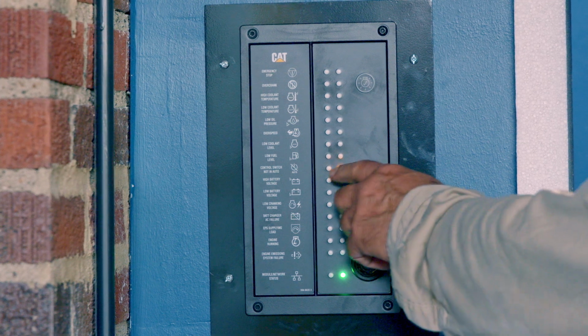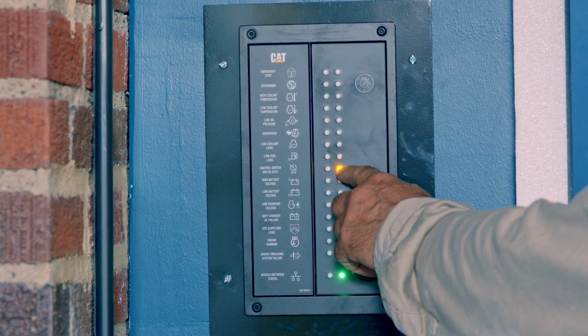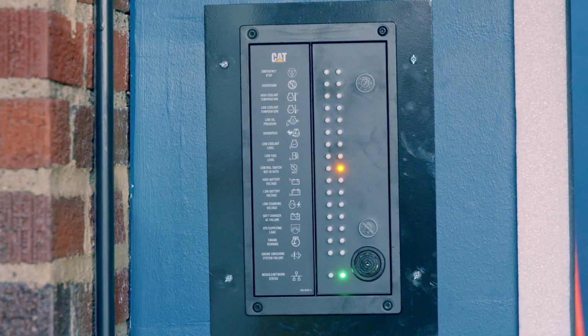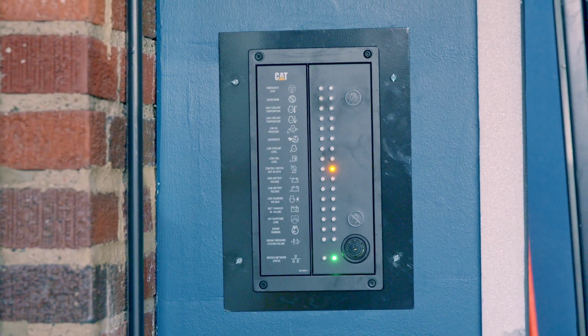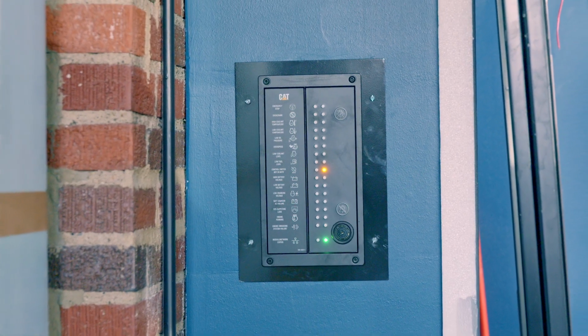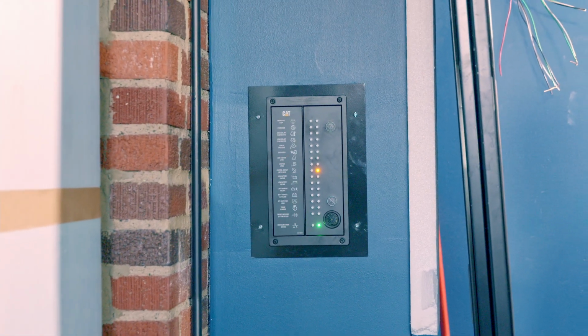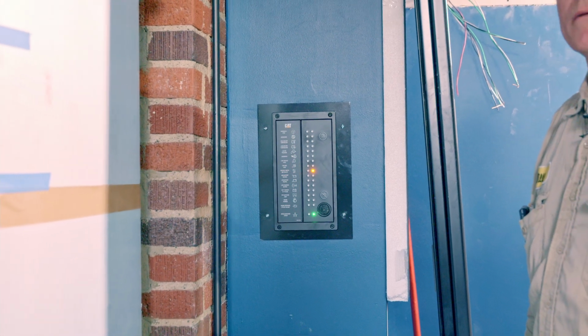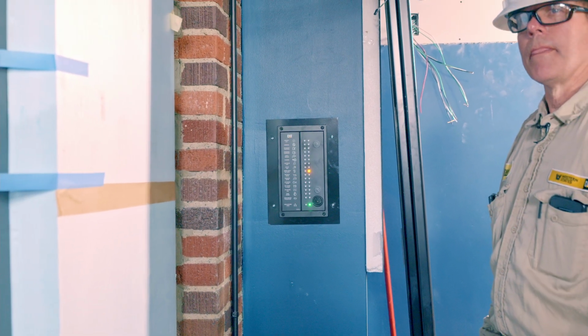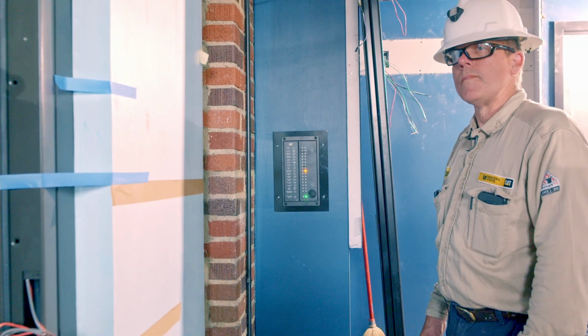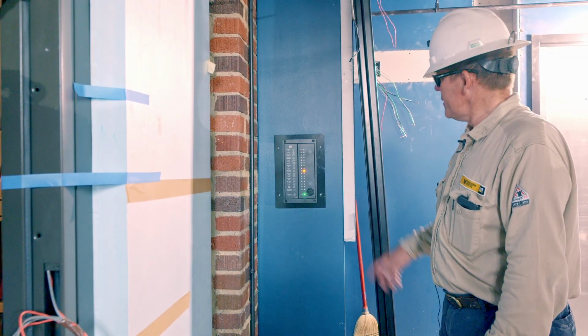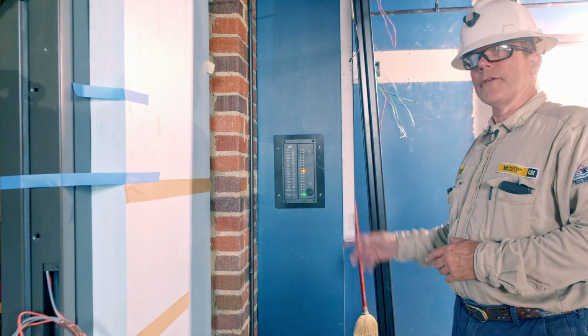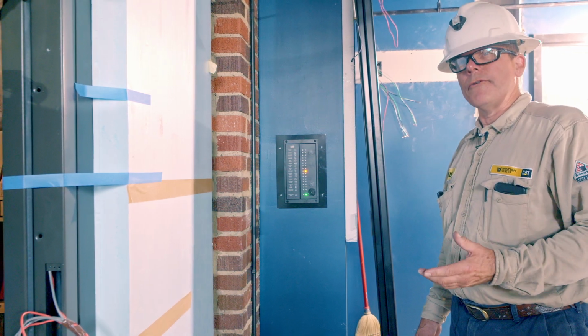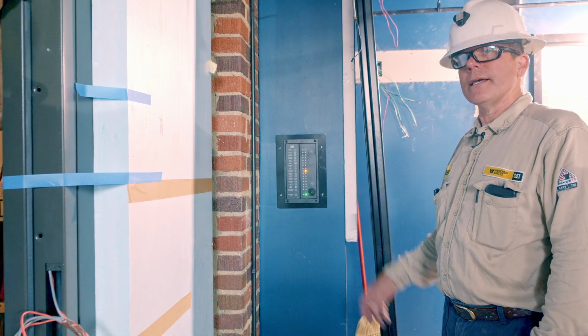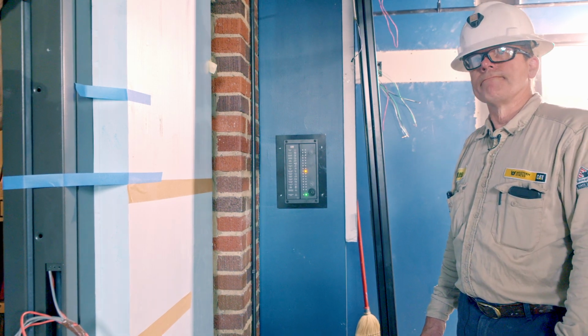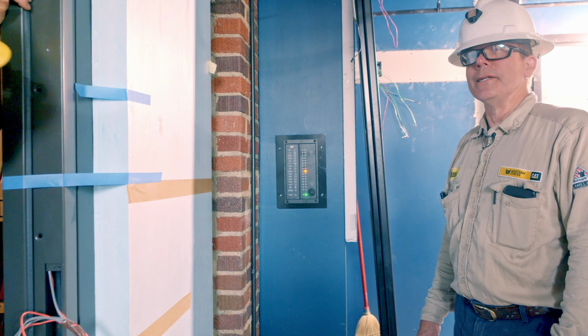And then if you got a fault, of course, this isn't the shutdown fault, but the generator is not available because it's not in auto. But the shutdown faults will be red and the warnings will be amber. Is that on a timer? No, nope. So once they acknowledge it, it stays like that? Yeah, once you acknowledge it. So that's a good way to remember if the thing's blinking or not. Say the horn fails, it burns out or something, and if that light's blinking, that means nobody's acknowledged it yet. But if it's solid, you know somebody's seen it. Yeah.